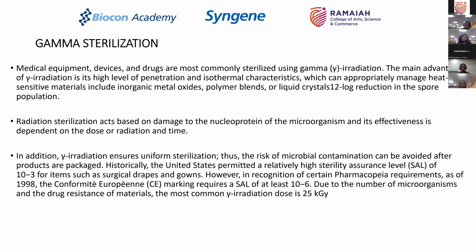Okay. Now, radiation sterilization, how does it act? We have discussed this in the past. It acts based on the damage to the nucleoprotein of the microorganism through penetration. So the photons penetrate into the nucleus, and into the cell, and then they bombard it and they damage the nucleoprotein of the microorganism, and therefore it is a good sterilization agent where it kills the microorganism. Its effectiveness, of course, depends on the dose of radiation or the radiation which is given to the component and the time.